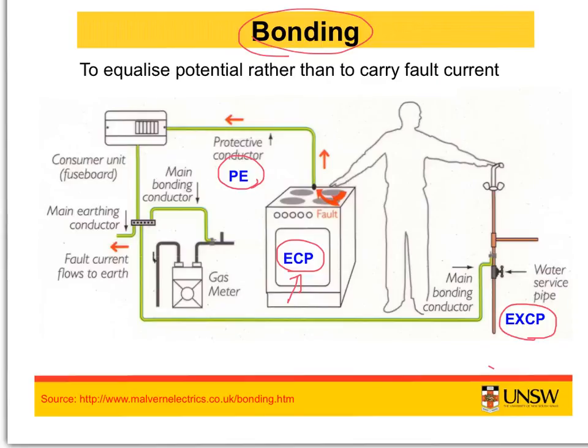Extraneous conducting part is any part of the metal which is not an electrical device but any conducting part such as the water pipes in the house. Okay, so the ECP can be touched, and it is usually not live, but it may become live when basic insulation fails. So it is also referred to as a non-current carrying metal part. Some examples of exposed metal parts are class 1 insulated appliances, armoring, lead sheath in underground cables, etc. The extraneous conducting part is also a conducting part that is not forming part of an electrical system. Examples are metalwork of gas, water and heating systems, and metallic frames of buildings.